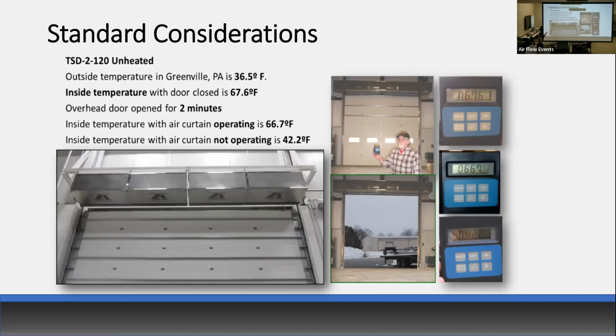Outside temperature this day was 36.5 degrees. Inside temperature with the door closed was 67.6. We open up that door, let the air curtain run for 2 minutes. After 2 minutes with that air curtain operating, it dropped to 66.7, less than a degree. Redid the test, turned that air curtain off. After 2 minutes without the air curtain operating, it dropped to 42.2 degrees. So they really do a great job at protecting that inside air, even if it's just an ambient air curtain for a large industrial application.